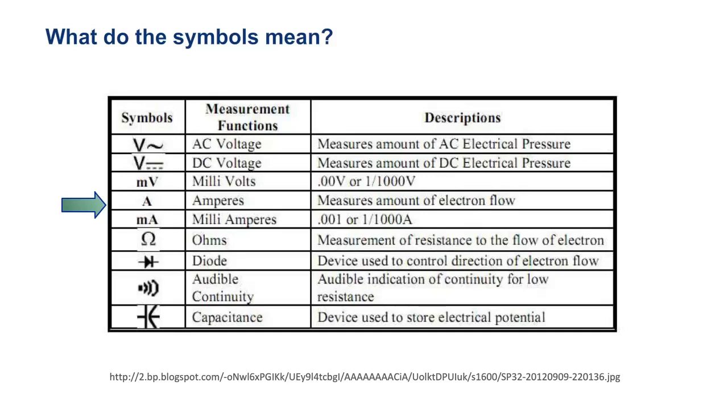Now, if you have a multimeter, I caution you, a multimeter that's rated up to 10 amps is not good for, say, a half-horsepower motor or smaller. It's not designed for AC period. That type of meter that measures with probes, you have to put the probes in the circuit, meaning you cut the wire. So we don't want to do that. It does us no good. It's designed for DC current where there's no in-rush. You put it into an AC current, and it's going to destroy the meter most likely. If you have a proper amp meter, it's the clamp-on type.